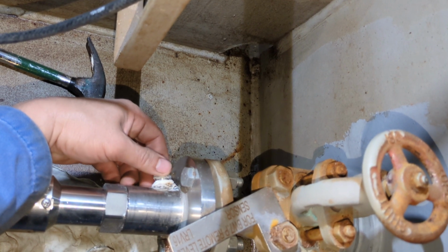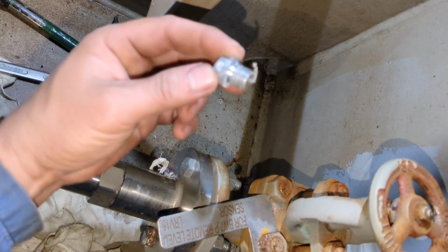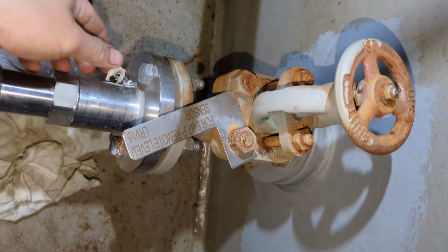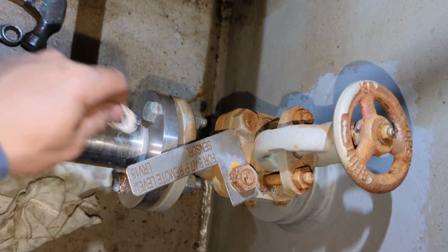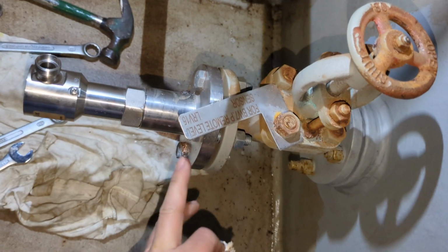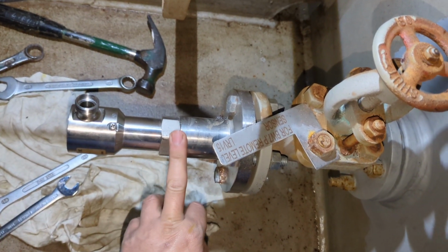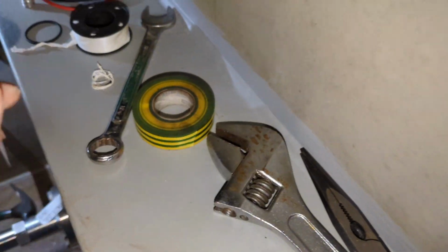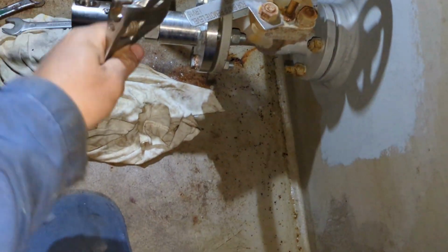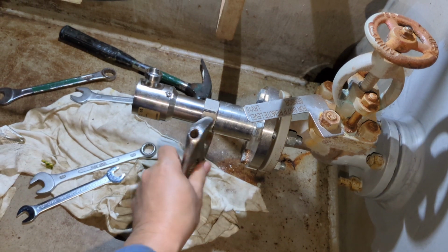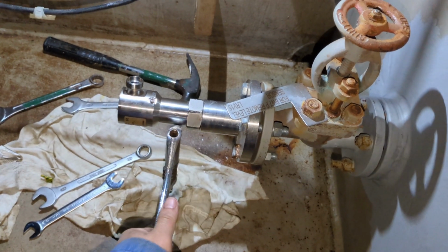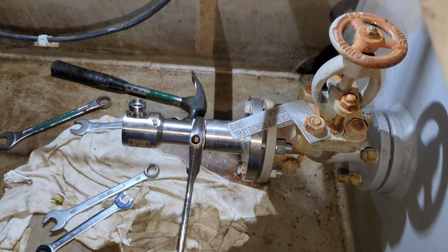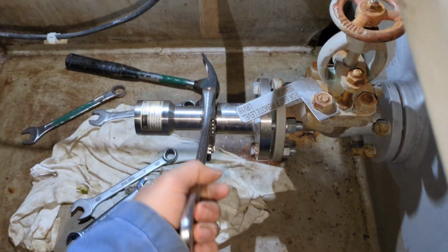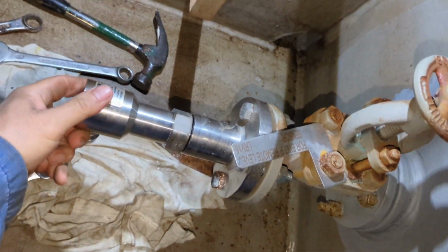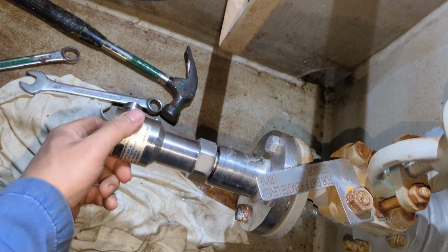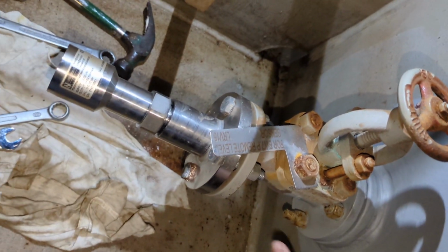Just little by little open it and feel if the water is coming out. By opening it, you will find a little drip of water, so it's verified that this has no water inside. In this way, we can replace this sensor without removing the flanges. From here, we can rotate this using a big spanner, little by little, guys. See, we can rotate this counterclockwise. Then you can rotate it little by little, but make sure that this is fully closed, so water will not come out.